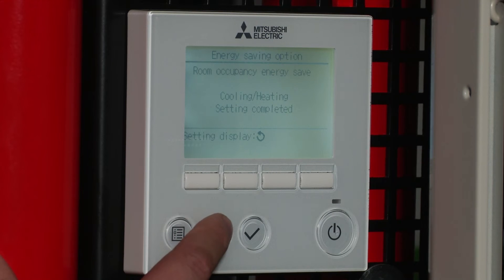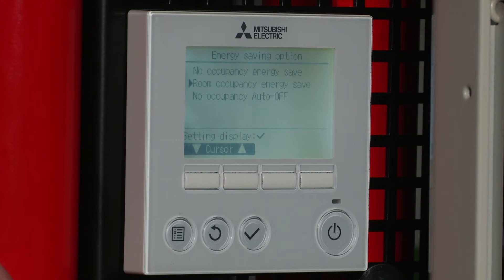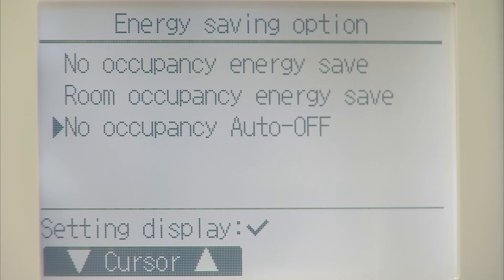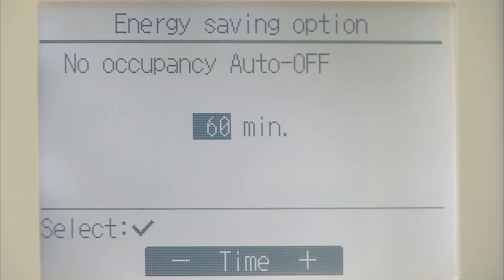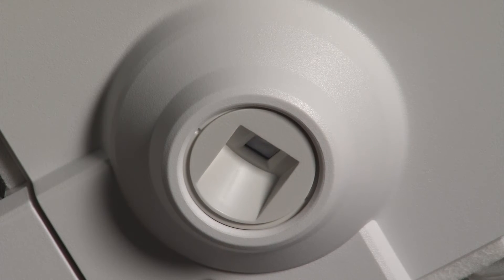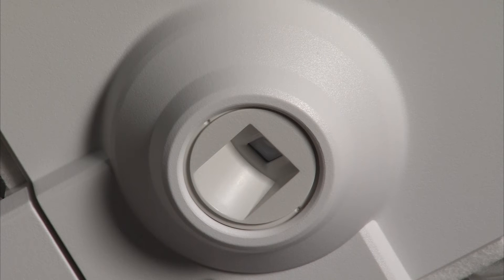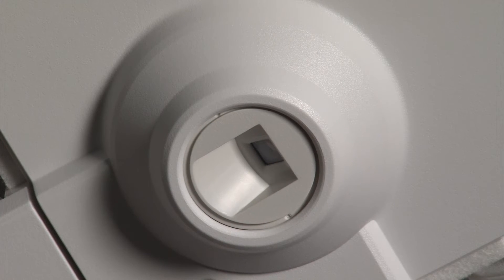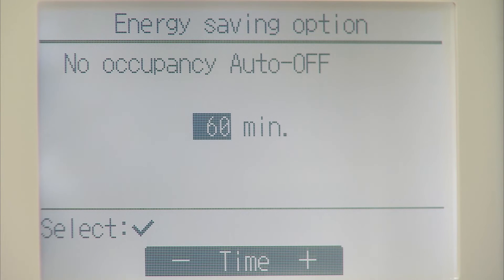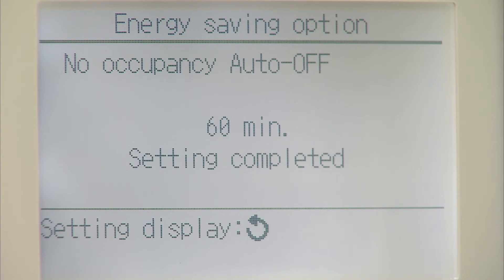Come back into the main menu. The last option there is no occupancy auto off. Select this option and what the unit will do is switch off after 60 minutes, or whatever time you set it for, where there's no occupancy in the room. This is not looking for movement — it is looking for a heat signature in the room, so it works slightly differently to what a PIR sensor does. When you're happy with your time, select that and come back out.